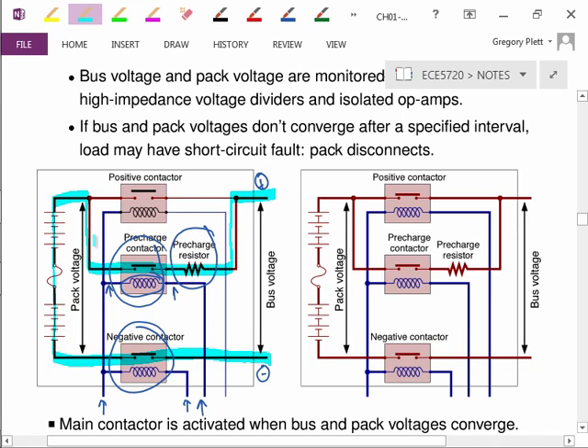This voltage will come close to the pack voltage, and only then is it safe to close the positive contactor, the main contactor. So that's what we've done now — all the contactors are presently closed, and I have a direct connection to the battery there.